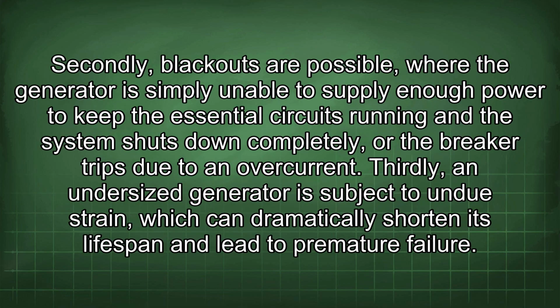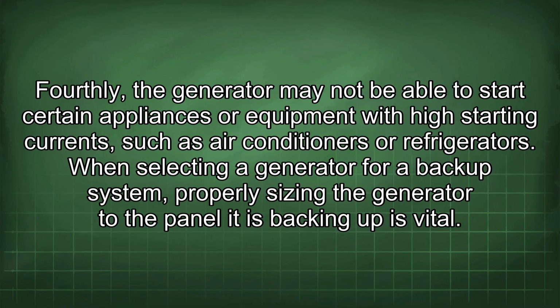Secondly, blackouts are possible, where the generator is simply unable to supply enough power to keep the essential circuits running and the system shuts down completely, or the breaker trips due to an overcurrent. Thirdly, an undersized generator is subject to undue strain, which can dramatically shorten its lifespan and lead to premature failure. Fourthly, the generator may not be able to start certain appliances or equipment with high starting currents, such as air conditioners or refrigerators.